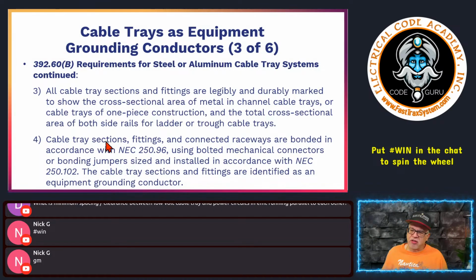Next, it says cable tray sections, fittings, and connected raceways are bonded together. So any raceways that feed into it, any fittings that connect it, any couplings that connect sections of a cable tray together, where they bolt together or however they fit, all of that has to be bonded in accordance with 250.96, the same way we would do feeder applications for raceways. So 250.96 isn't new for us, right? Again, we do this with feeders, with lock nuts and all this kind of stuff. We do that all the time. Y'all are used to that, making sure that you remove any paint or enamel that may inhibit the connection from metal to metal. You'll use lock nuts on raceways that cut into the metal, so the enamel does not need to be removed because it cuts into it.